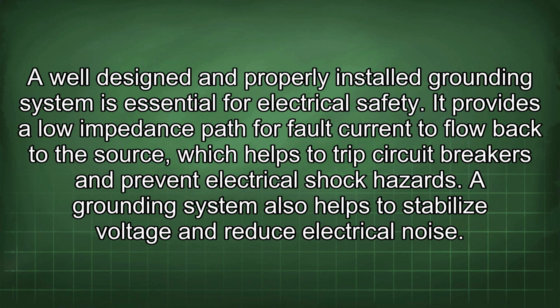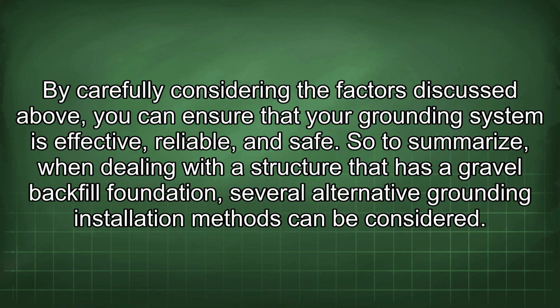A well-designed and properly installed grounding system is essential for electrical safety. It provides a low impedance path for fault current to flow back to the source, which helps to trip circuit breakers and prevent electrical shock hazards. A grounding system also helps to stabilize voltage and reduce electrical noise. By carefully considering the factors discussed above, you can ensure that your grounding system is effective, reliable, and safe.